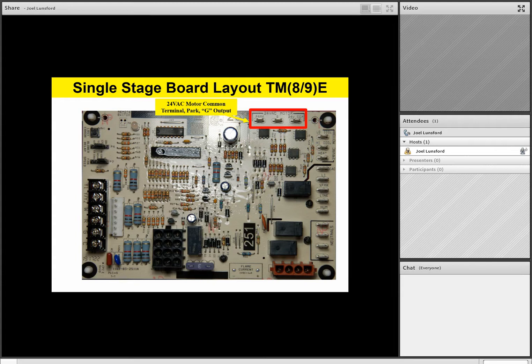As we move around to the side of the board, we see that we've got some blower speed tap selections for low cool speed, high cool speed, and heating speed. Again, these are 24 volt outputs to command the motor what to do. Below that, we have a 120 volt electronic air cleaner terminal. That EAC air cleaner terminal will be energized anytime the fan is running. It allows a 120 volt output from the board to energize an electronic air cleaner anytime the fan is running, if it's so desired.